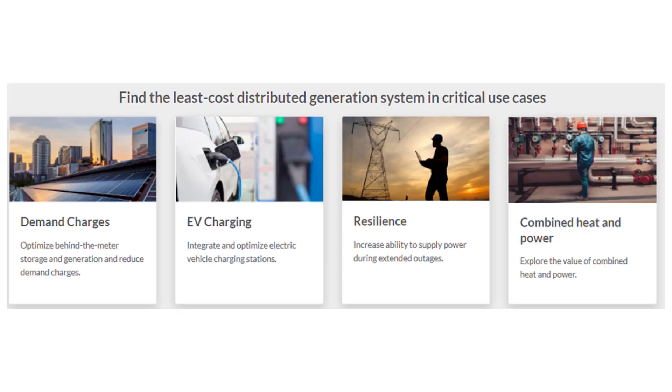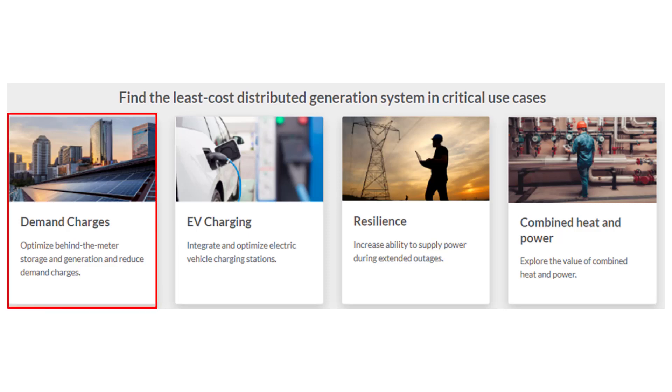Homer Grid's main value proposition is reducing utility charges by using solar and storage to shift and smooth peak utility usage to times when rates are lower. Demand charges are based on the maximum load typically for just 15 minutes. Time of use rates provide less expensive electricity at certain times. Solar and storage together can reduce both these rates.